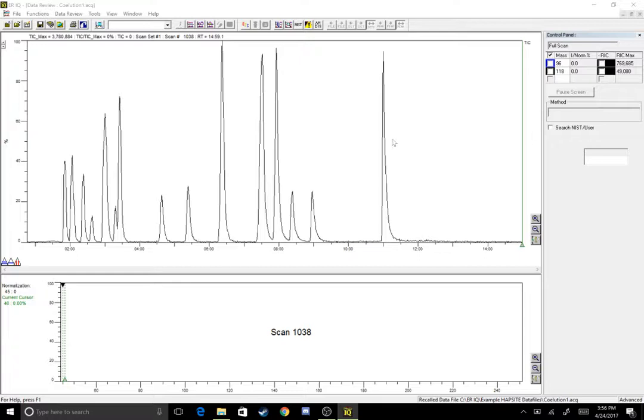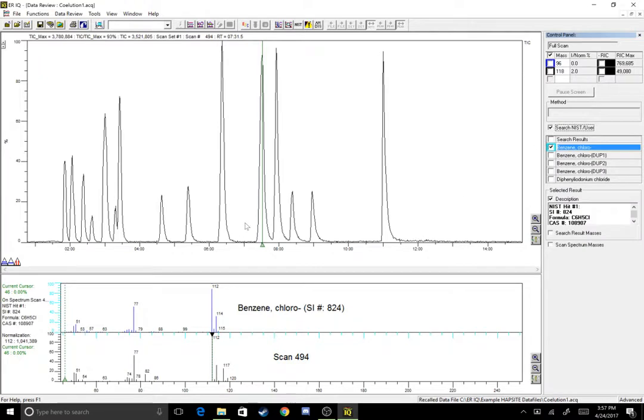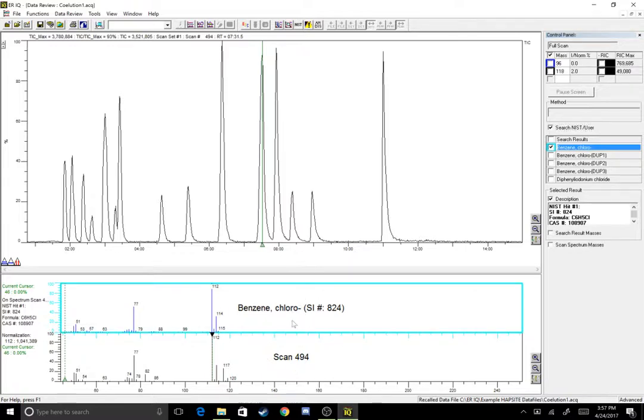Since I have seen this before I know exactly where to go. It's this peak at about 7 minutes and 30 seconds, but before you do that the first thing you should always do on this software is to do your search NIST slash user. This is essentially just telling your NIST database to reference where you have the scan selector set at and it's comparing that to the NIST library. Your scan to the NIST library scan up above it.